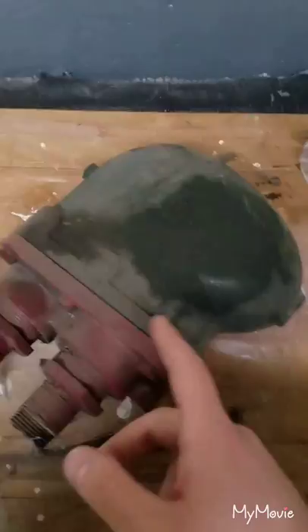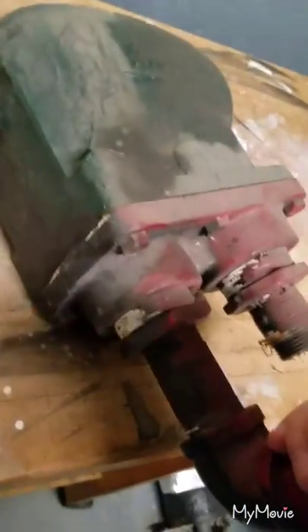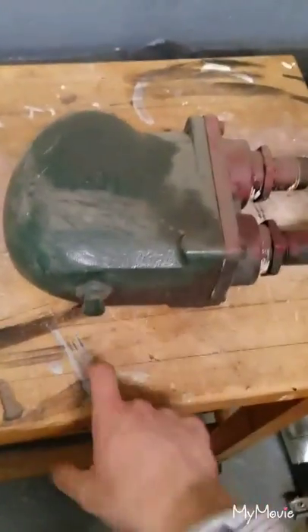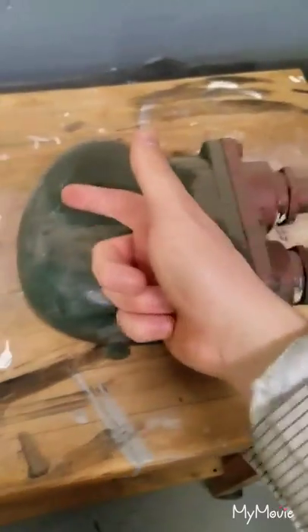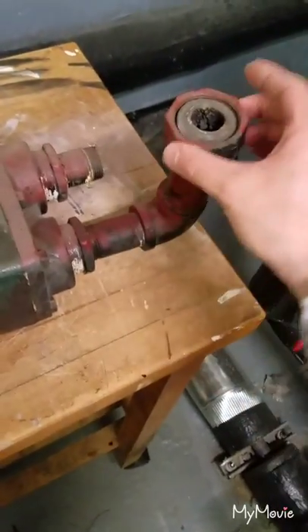I have one here. Now, I will try to get these bolts undone. I don't know if I can, because usually they're very torqued down. You might have to heat them up with a torch. Usually the steam trap is always positioned this way with this plug on the bottom. Steam comes in the top here, and condensate exits through the bottom here.